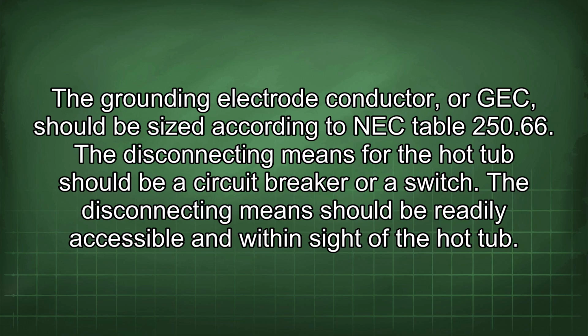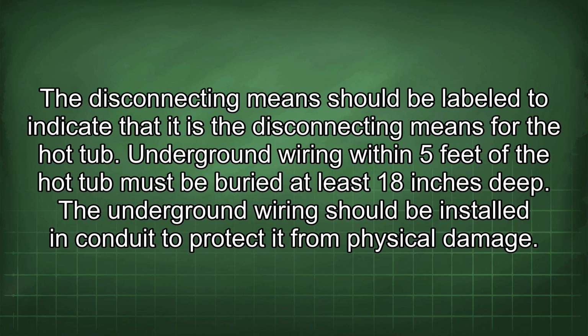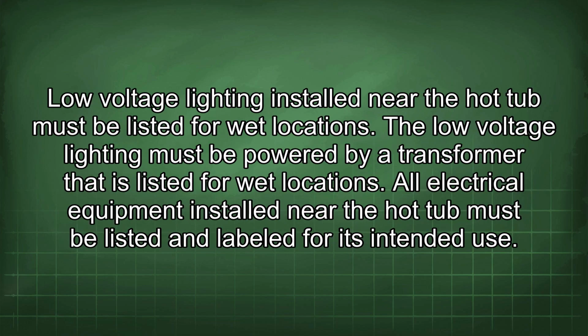The disconnecting means should be readily accessible and within sight of the hot tub. The disconnecting means should be labeled to indicate that it is the disconnecting means for the hot tub. Underground wiring within 5 feet of the hot tub must be buried at least 18 inches deep. The underground wiring should be installed in conduit to protect it from physical damage. Low voltage lighting installed near the hot tub must be listed for wet locations.